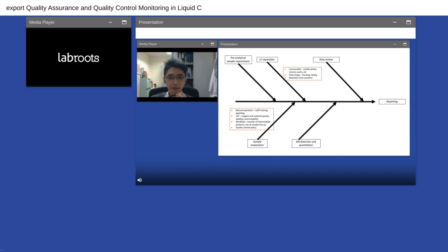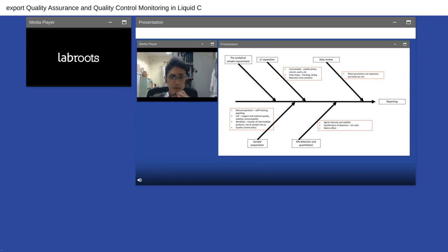For LC separation, consumables play a big part. Peak shape and retention time are things we need to look out for. For LC-MS detection, signal intensity and stability — within batch or between batch — are very important. Qualification of detection uses the ion ratio, and matrix effects are also important parameters. Data review is one of the most critical parts in the entire workflow, because we need to know which parameters are important. We need to stratify the importance of these parameters to have an efficient quality assurance policy.